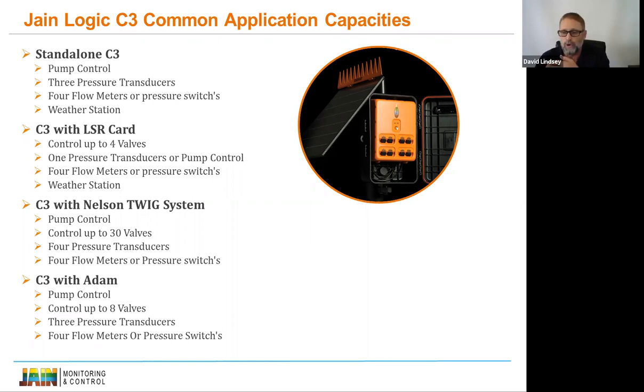With the Adam controller, it's an IP-addressable component, and I'll show you a picture of one later. We literally have one deployed in the state of California, there's just not that much need for it. But we do get pump control, and we can control up to 8 valves with a single Adam. The Adams can be stacked though, so we can get almost an unlimited amount of valves based on the memory of the C3. I'm not sure what our limit is there, but let's say maybe 30. We also get 3 pressure transducers, and 4 flow meters or pressure switches as well with that.